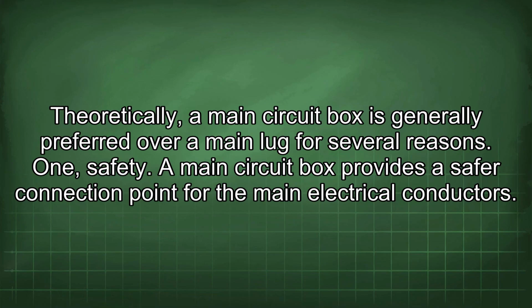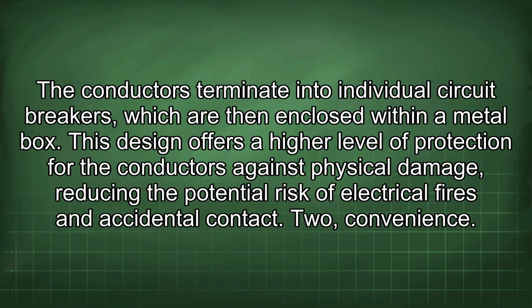Theoretically, a main circuit box is generally preferred over a main lug for several reasons. 1. Safety. A main circuit box provides a safer connection point for the main electrical conductors. The conductors terminate into individual circuit breakers, which are then enclosed within a metal box. This design offers a higher level of protection for the conductors against physical damage, reducing the potential risk of electrical fires and accidental contact.